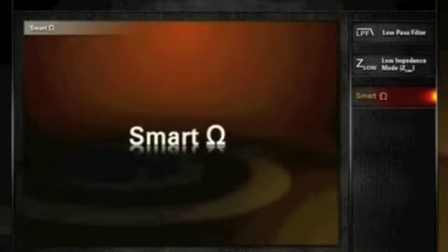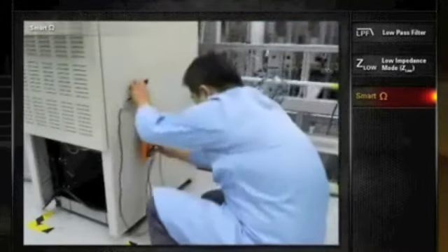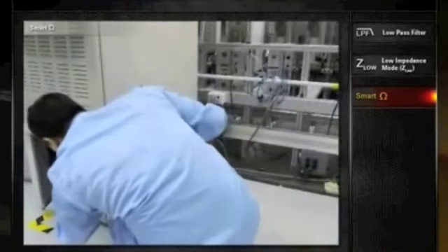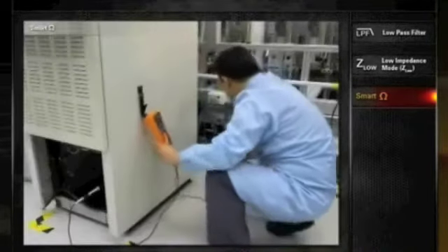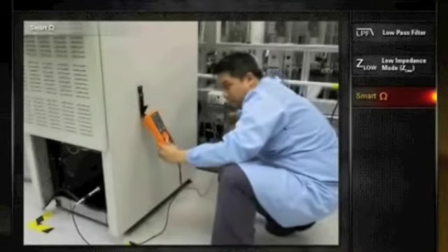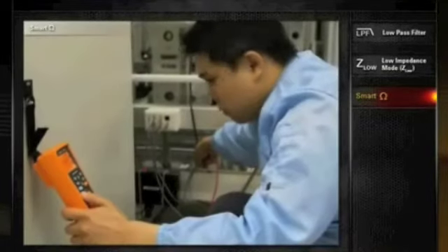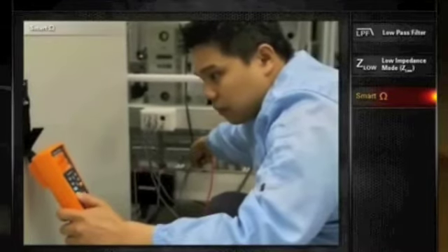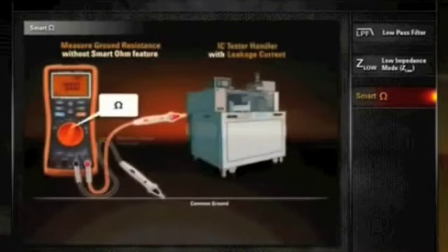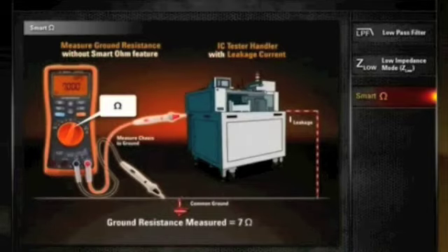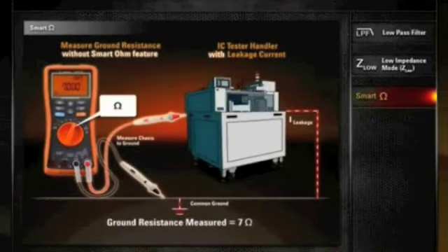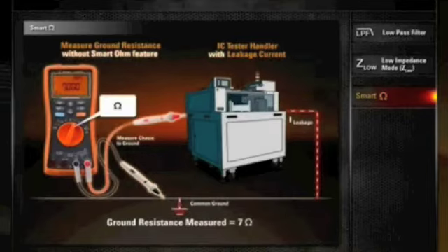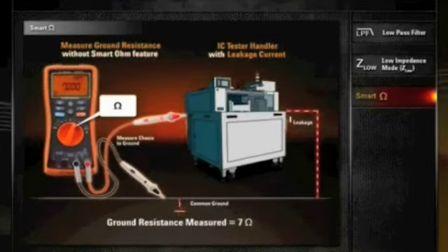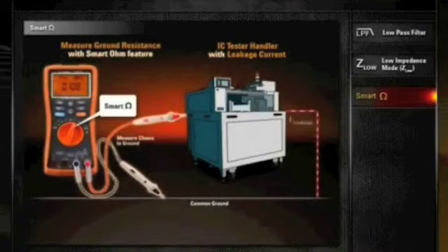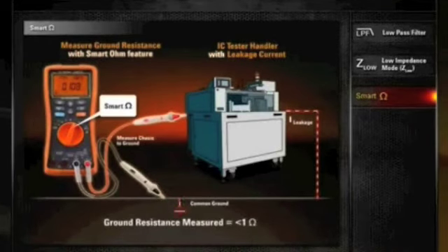Smart Ohm. Ground continuity. In semiconductor manufacturing, ICs under test are exposed to electrostatic discharge due to constant metal-to-metal contact in the IC tester. Technicians who perform weekly checks between the tester's grounding and common ground may find inaccurate ground resistance measurements due to leakage current in the test system. The U1270A's Smart Ohm function is capable of providing accurate ground resistance measurement despite the presence of leakage current.